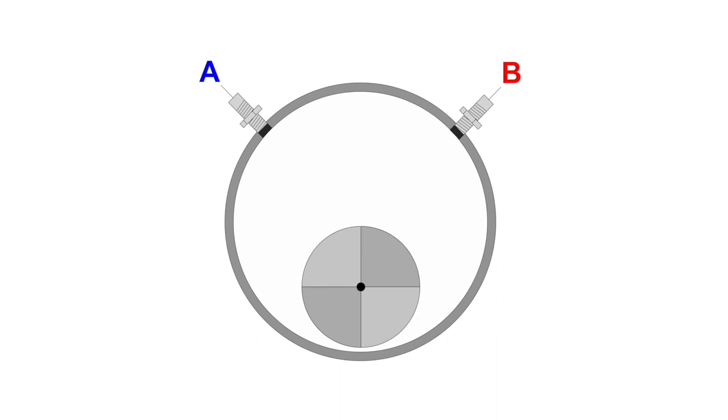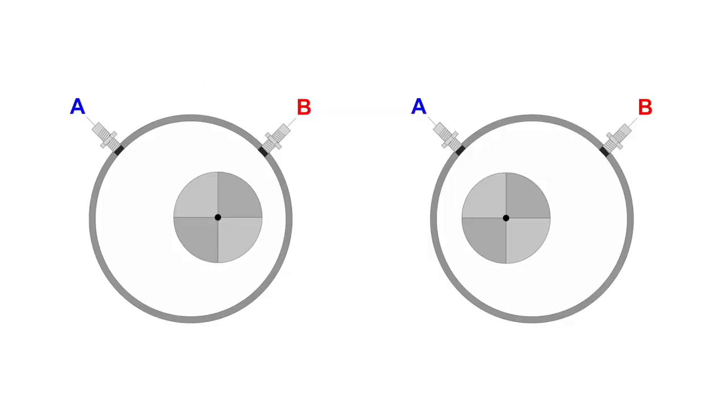When we use two proximity sensors, then we can display the position of shaft in bearing. This is zero machine speed, less than 100 RPM usually. Shaft is assumed to be at the bottom. Normal positions on nominal speed. The position corresponds to the direction of rotation. The position tells nothing about vibrations. It is just the DC part of signal.